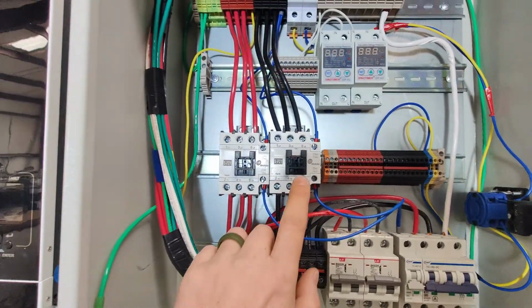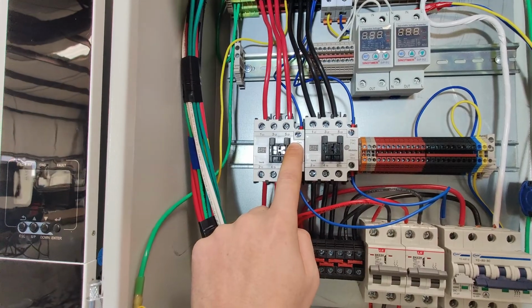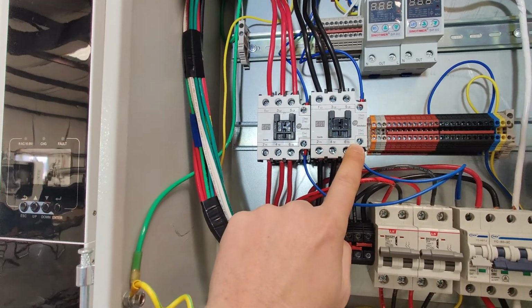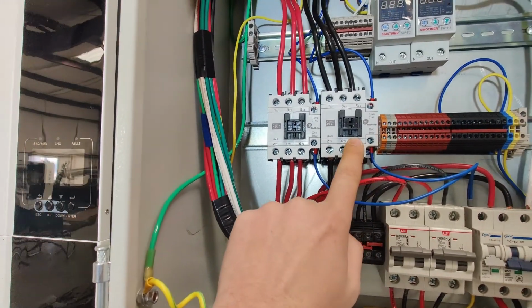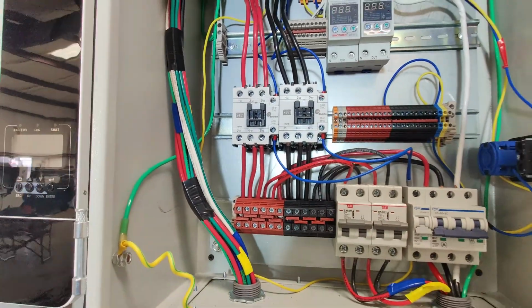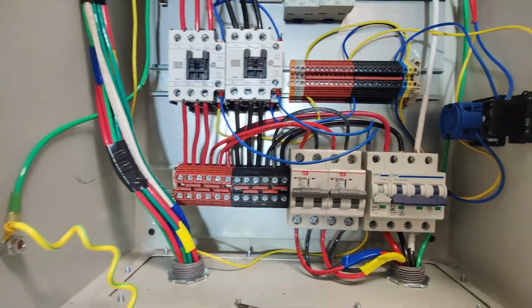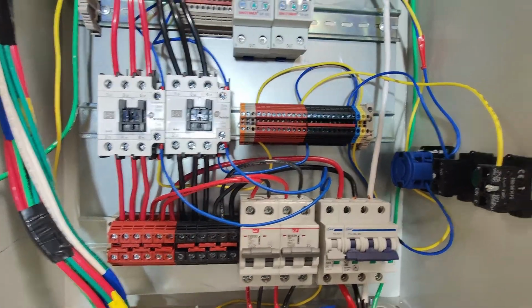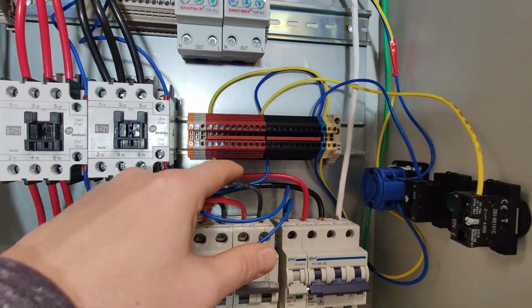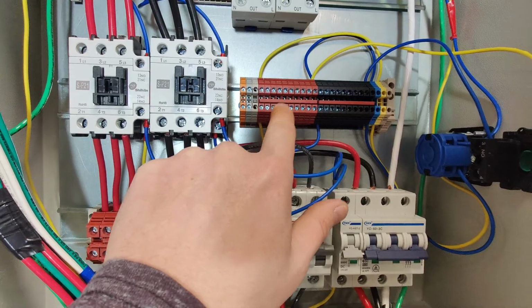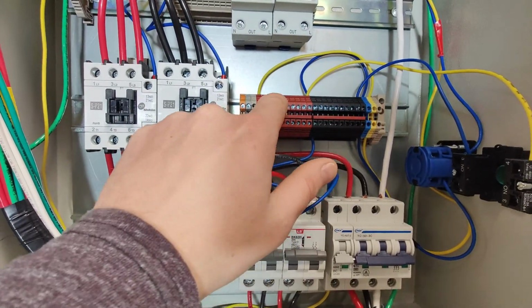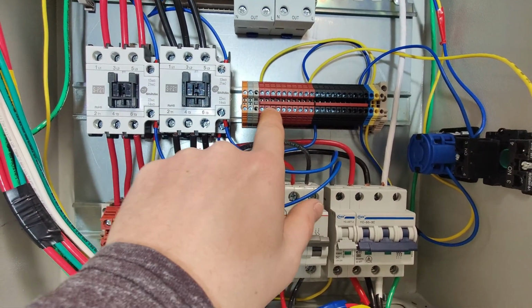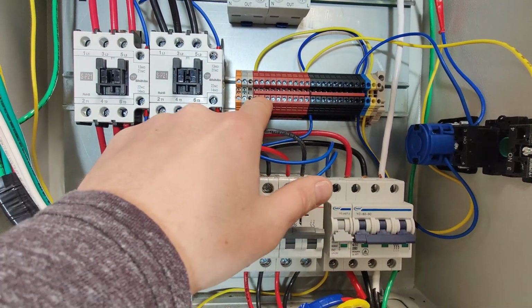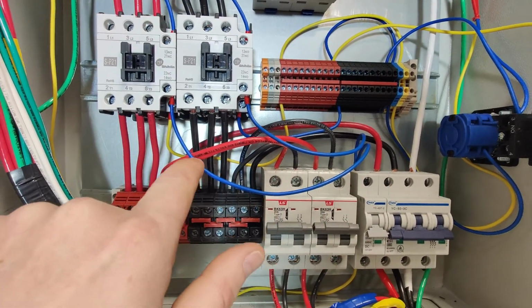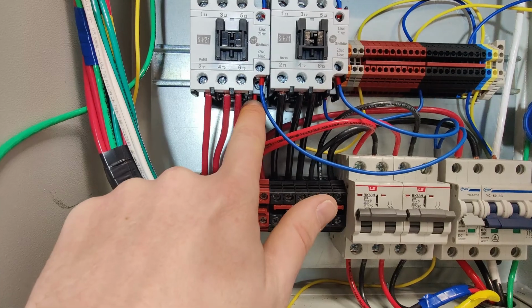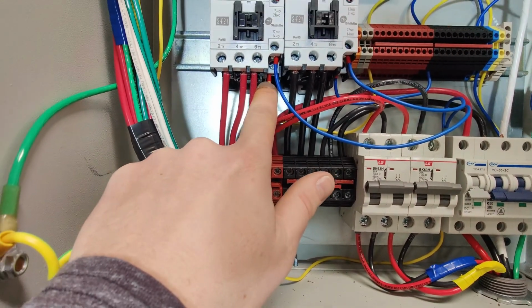And like I said, we're going to be using one contactor for one leg and the other contactor for the other leg. And we'll come back when this is all ready to rock and roll. Just kind of wanted to show this a little bit. I'm about halfway through this. So what I've done is I've run a yellow wire out of this hot side. And on this bus bar, it doesn't matter whether you come out of the top or the bottom. In this case, I'm coming out of the bottom and coming through the bottom side of the contactor down here to this normally open side of the contactor.